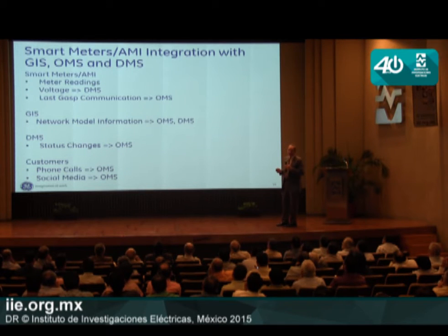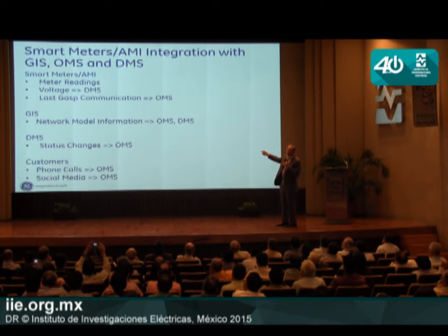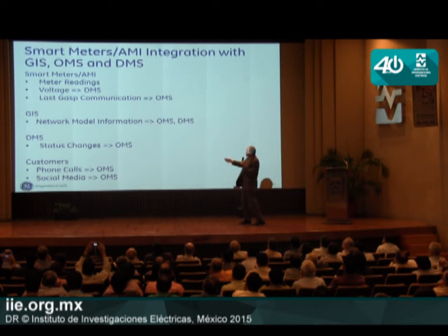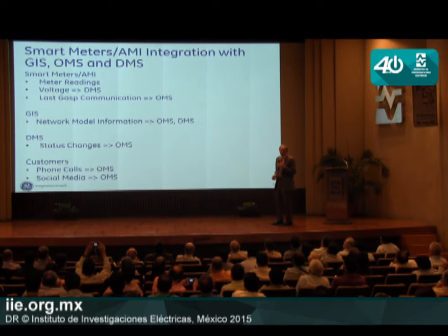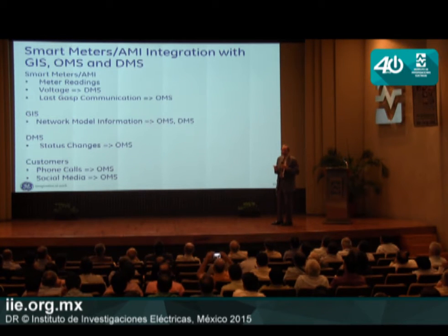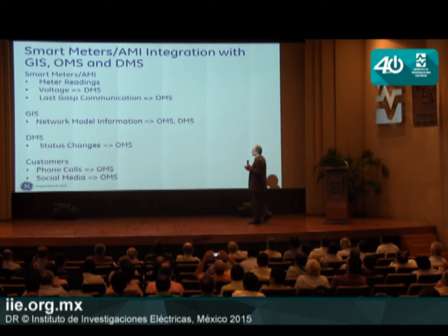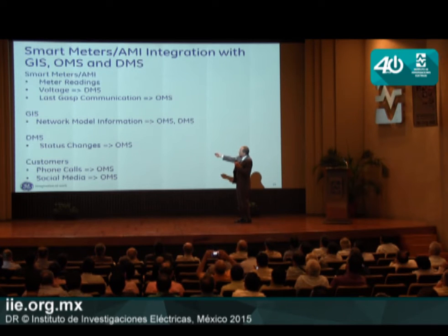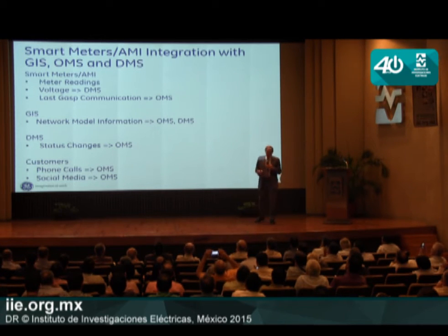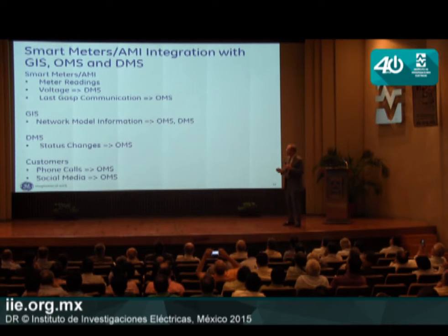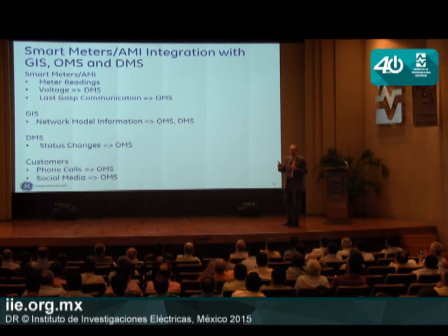Well, first off, we need to invest in 5 key components. Smart meters, metering communications, which we call automated metering infrastructure, and 3 systems: the geographic information system, outage management system, and distribution management system, right? But it's not the value of those separately, it's the integration of those which makes the grid more resilient. For instance, I need from the meters not just the meter readings, but I need the voltage from certain meters at the ends of certain feeders to put in a network model in the distribution management system. When I do volt-var control, I need to know the voltage at the end of the feeder.